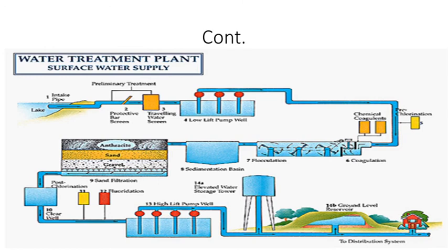Why is it a slow sand filter? Because the rate of filtration for that water is slow, so the filter is called a slow sand filter. The second type is the rapid sand filter, where the rate of filtration is high. The composition of both filters is the same: a drainage system, then gravel, then sand. But the cleaning of the two filters is different. Cleaning of the slow sand filter is different, and cleaning of the rapid sand filter is different.